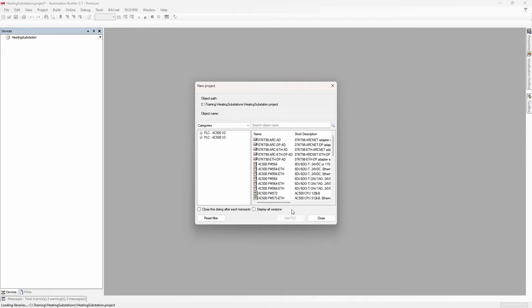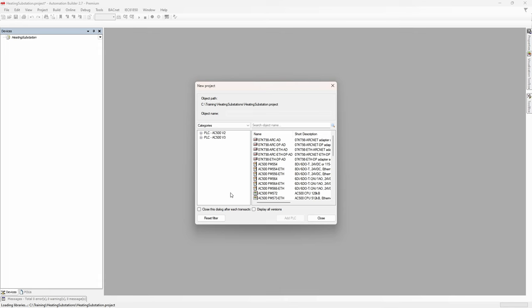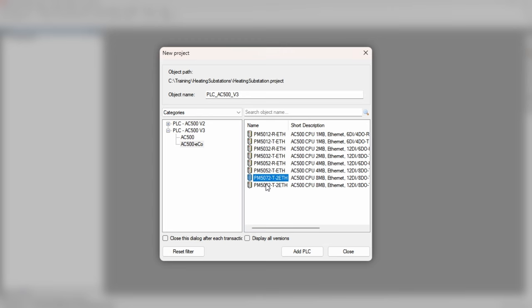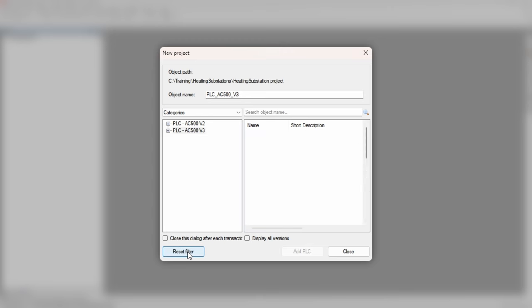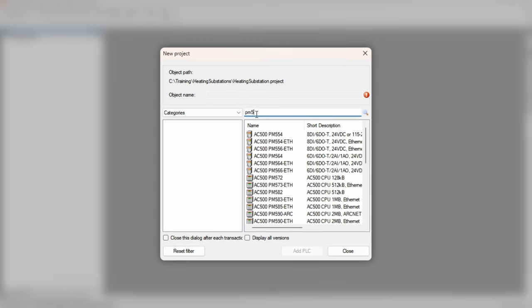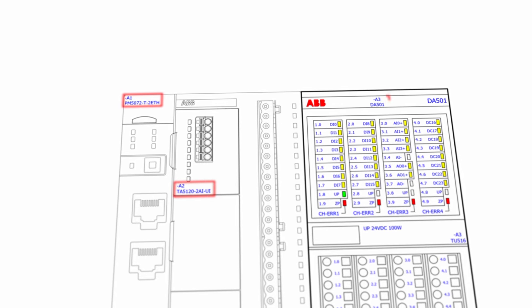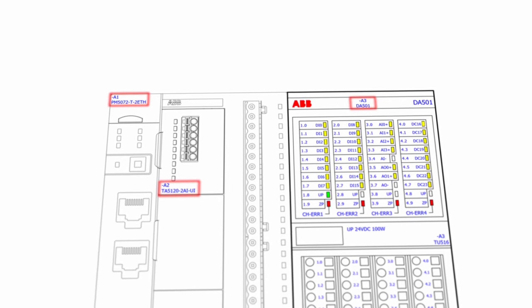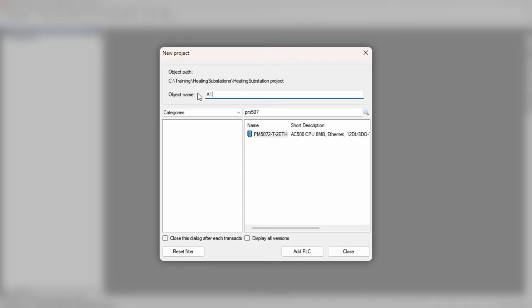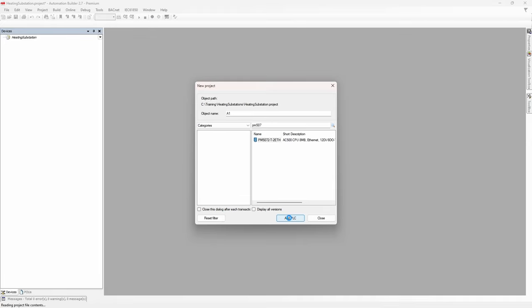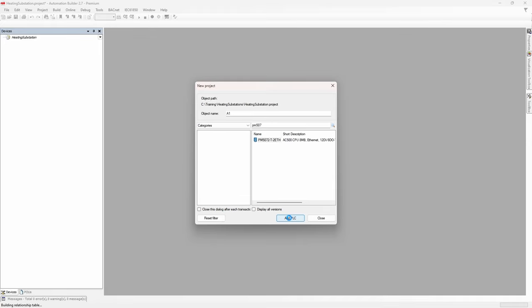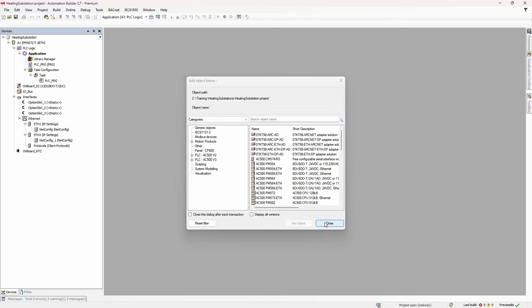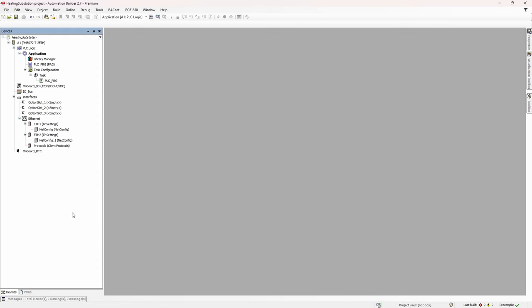And since we have selected AC500 project as a template, software offers us to select the specific device we're going to use in the project. If you know where to look, you can filter by category and select CPU model straight away, or you can search for desired product by typing the name. Since we already have project electrical diagram, it's a good idea to give devices the same name as in the schematic. And after hitting add PLC, Automation Builder will create default hardware configuration structure for PM5072 CPU.